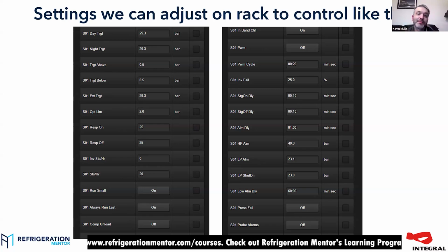And that, because especially on CO2, the enemy really is the plant stopping when you don't want it to, because once you stop flow, you can't sense what's going on in the gas cooler anymore. You can't sort of maintain the conditions that you need to get the system running smoothly. You want to keep that running as much as you can. Obviously, you do need to stop it eventually when the compressors get out of their envelope, but it pays to give it the maximum opportunity.